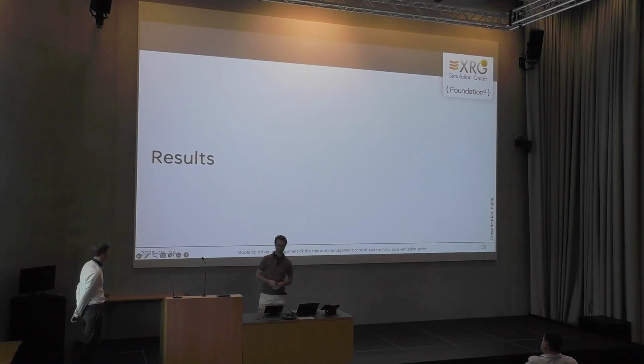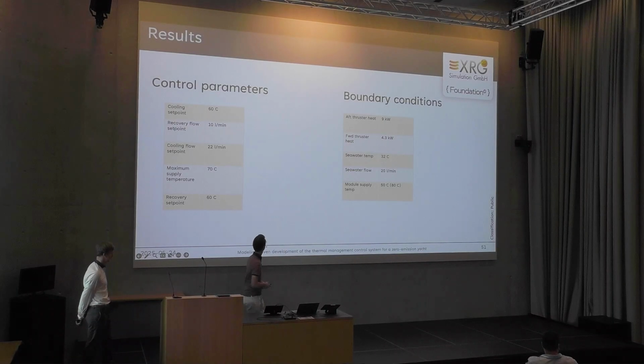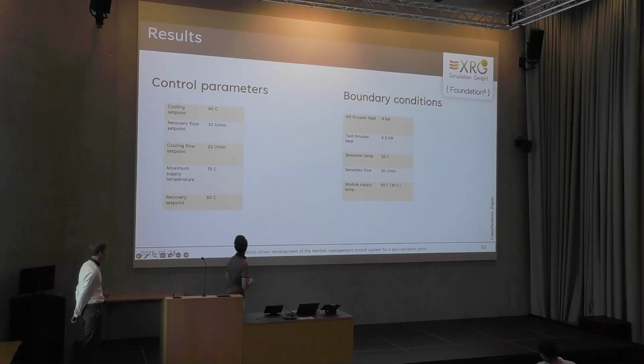Then we run that control against the simulation from XRG with the following parameters. We want to cool the thrusters to 60 degrees. We also want to have the recovery temperature at 60 degrees. We allow for 70 degrees into the thrusters, and we want 10 liters per minute in recovery mode, 22 liters per minute going through them in the cooling mode. And we say the aft thruster is producing 9 kilowatts, forward 4.3, seawater is at 33 Celsius. There is 20 liters per minute going through the heat exchanger that you saw earlier. And the module starts with 50 going into it, but we'll ramp that up to 80 as you'll see here.